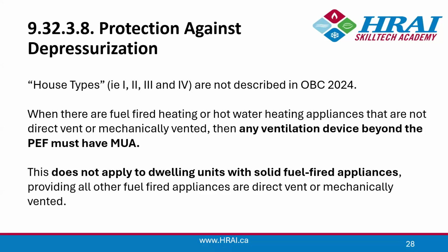So what we're saying here is, if it's not mechanically vented or direct vent, if you have a clothes dryer, if you have a range hood and they're vented to the exterior, and it's not the principal exhaust fan, of course, because these are supplemental appliances, they will need makeup air. So it gets messy right away, which pushes us back to direct vented appliances, or no combustion appliances, as in the case of heat pumps and so on.